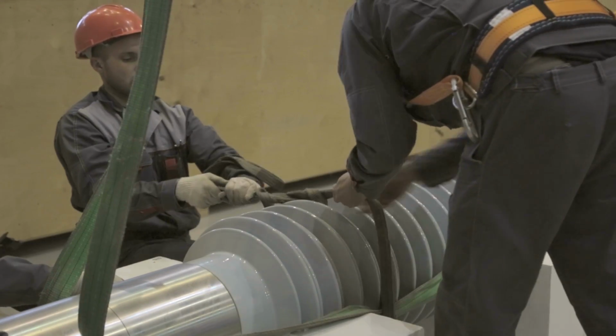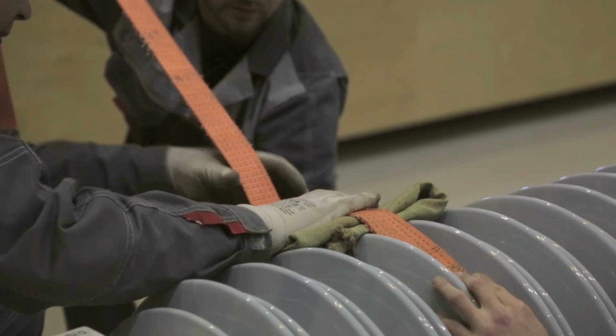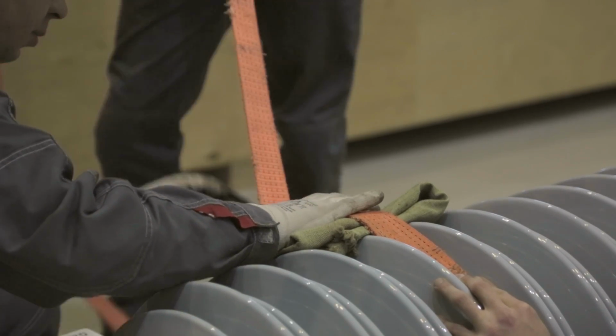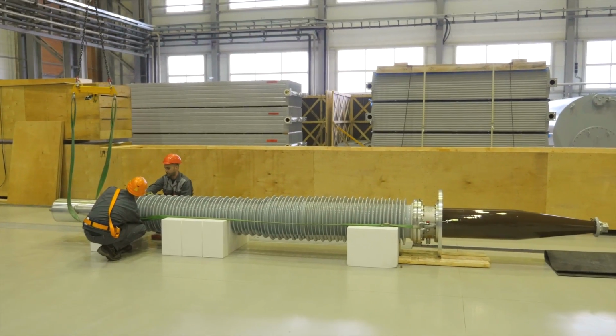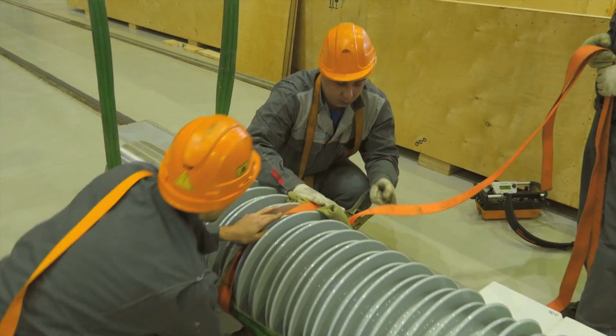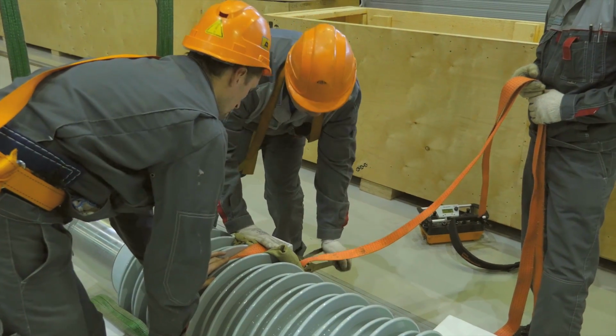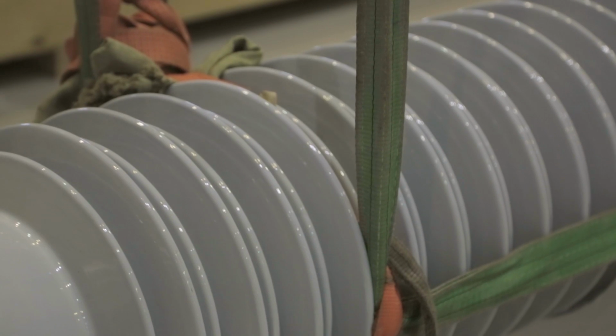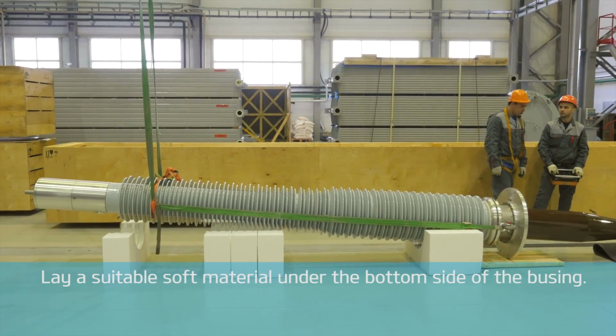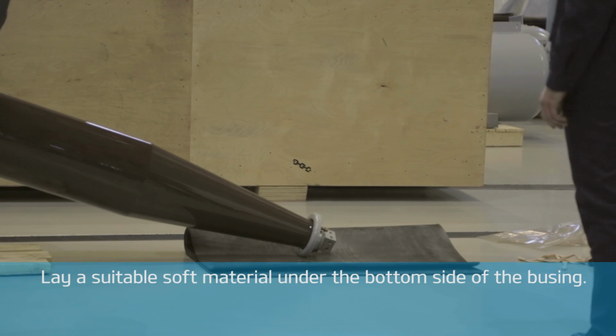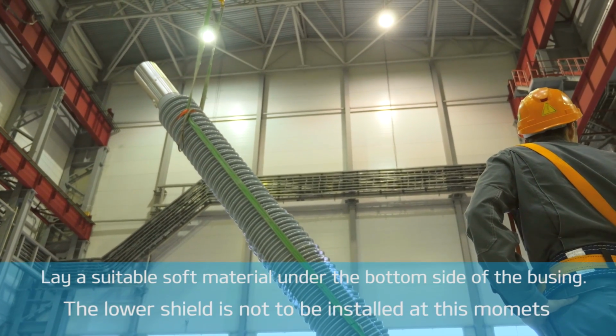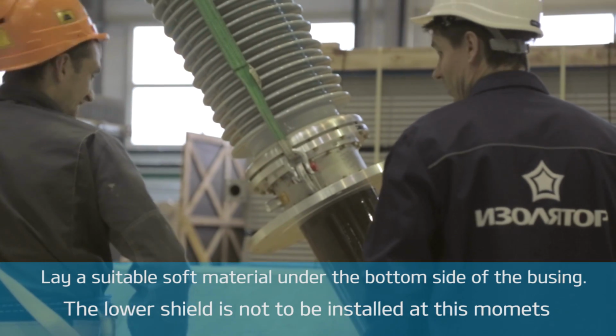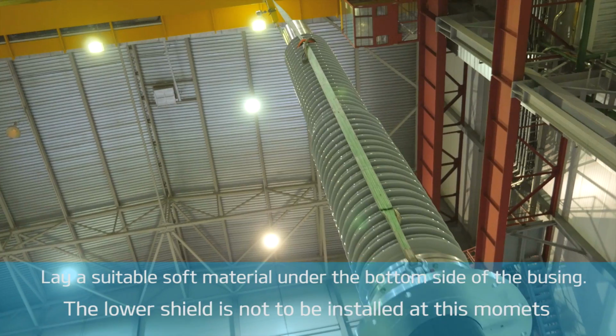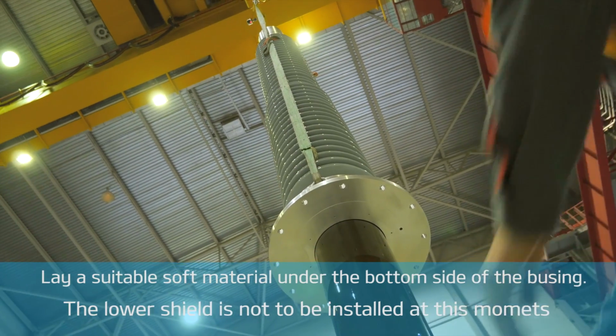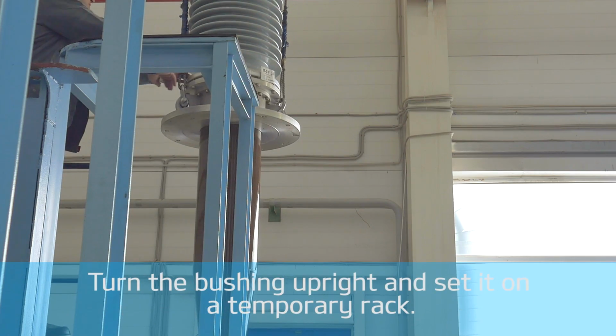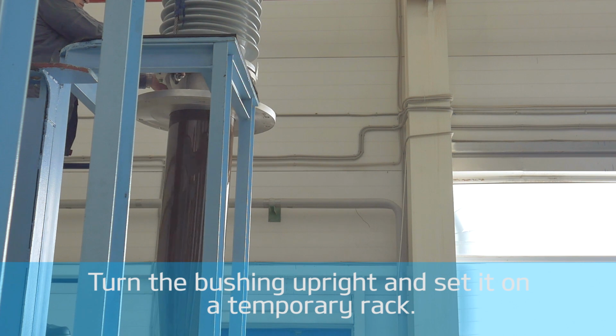Fix the tows on the coupling handles, can be lugs or eyebolts. Stretch the toes along the housing and fix them with another tow to eliminate slipping. If necessary, use an additional tow for fixing. Lay a suitable soft material, rubber or felt, under the bottom side of the bushing. Please note that the lower shield is not to be installed at this instance because it could be damaged with a high probability. Avoiding the bottom slipping, steadily turn the bushing upright and set it on a temporary rack.